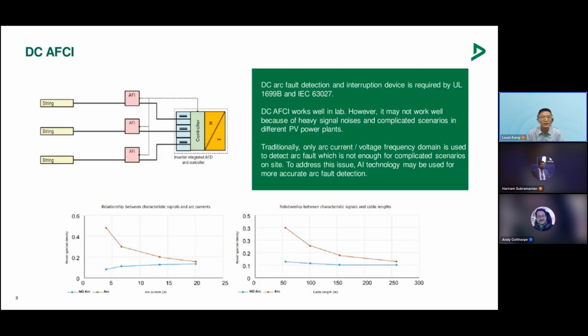DC arc fault detection is required to be installed in a PV power plant by some standards like UL 1699B and IEC 63027. In distributed PV power plants, this arc fault detection and interruption device is usually integrated in the PV inverter. DC AFCI works very well in the lab. However, it may not work so well on site because of heavy signal noise and complicated scenarios in different PV power plants. Traditionally, only arc current voltage frequency domain is used to detect arc fault. This is not sufficient for complicated scenarios on site. To address this issue, I think AI technology like deep learning with a huge amount of input data may be used for more accurate arc fault detection.